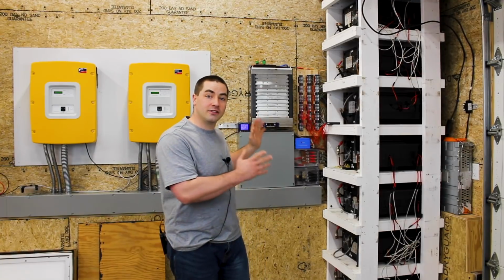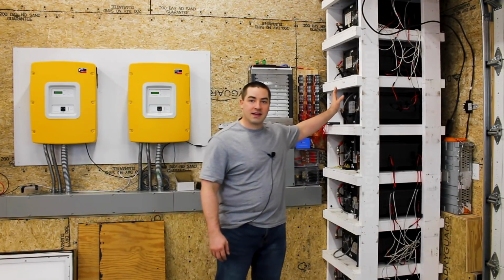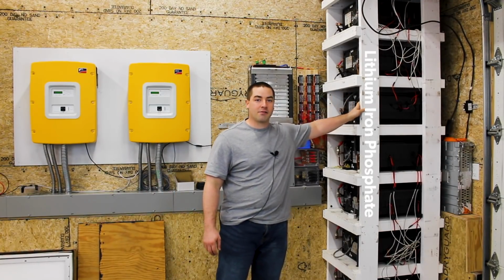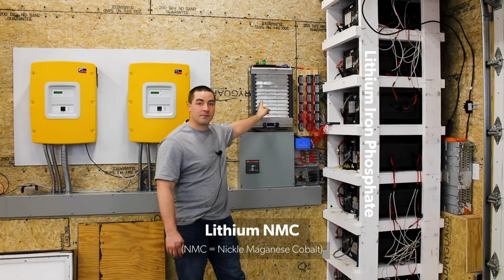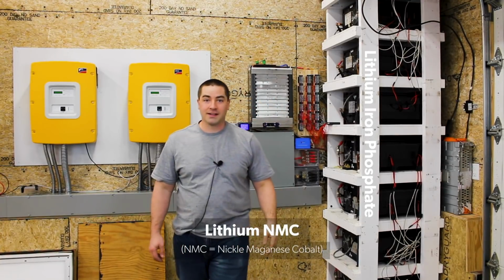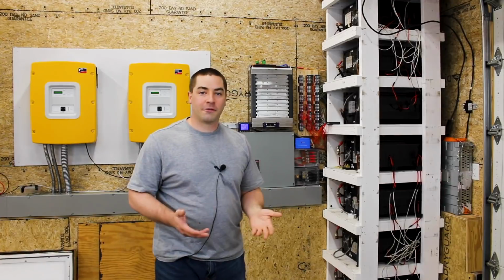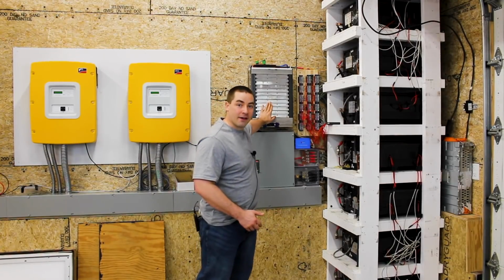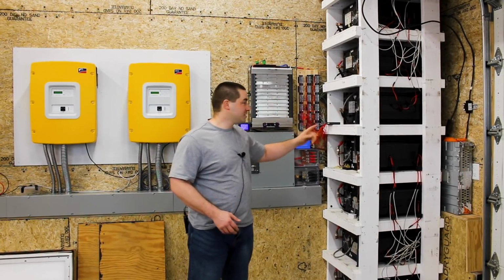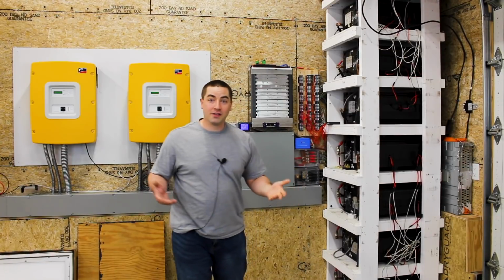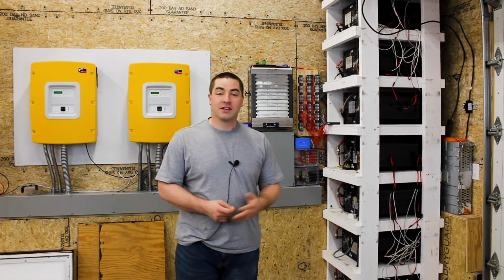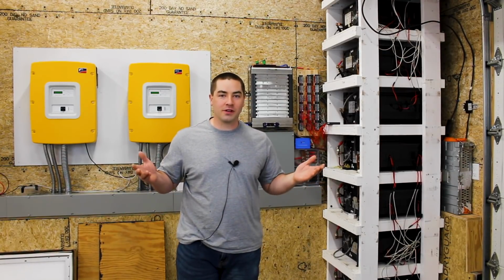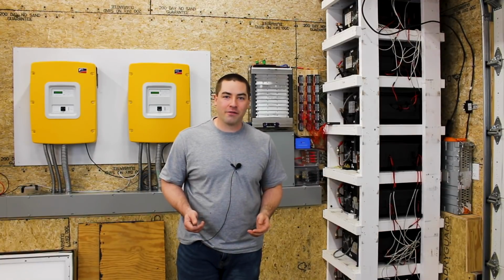But there's another reason I don't charge to 100% and discharge to 0%, and that is these are different chemistries. This is a lithium iron phosphate battery bank, and this is a Li-NMC battery bank. Different chemistries have different charging profiles. This battery has a different maximum voltage than that one, and they also have different minimum voltages. So what is the actual usable amount of capacity that I have available?